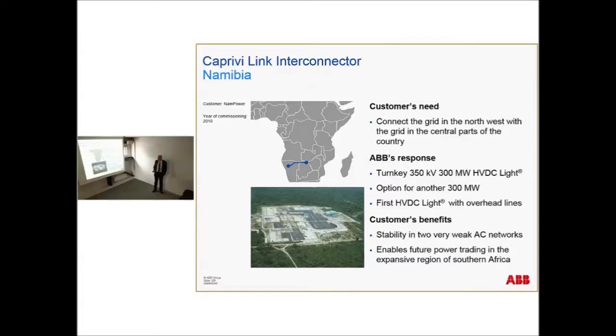generation. And it's worth mentioning here that in this area, there is also a lot of lightning activity that will short circuit the overhead line. The system is very weak at both ends. So originally this was ordered as what we call an HVDC classic system, but after the system studies it was agreed that we must have an HVDC light system in order to be able to control it. And this will enable future power trading in this area in Africa.